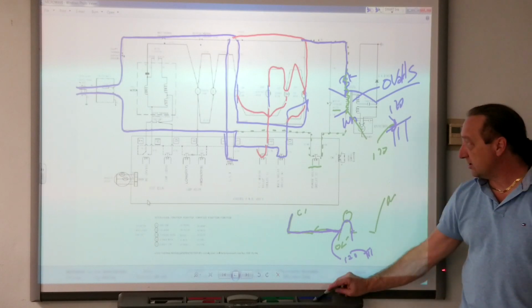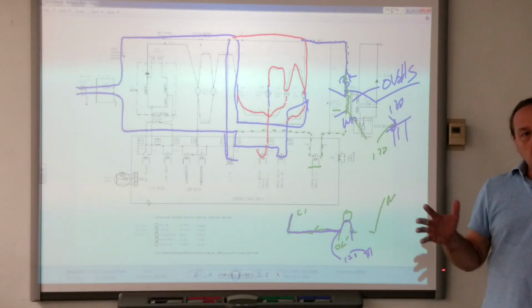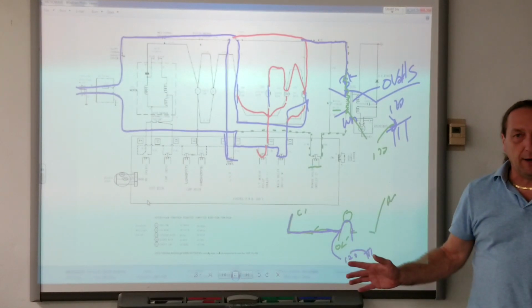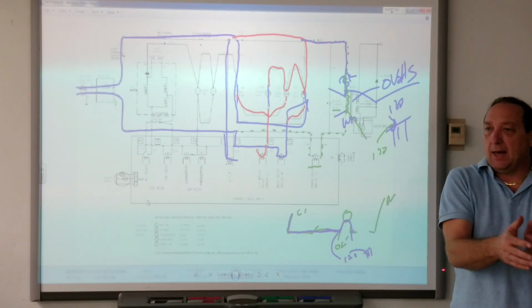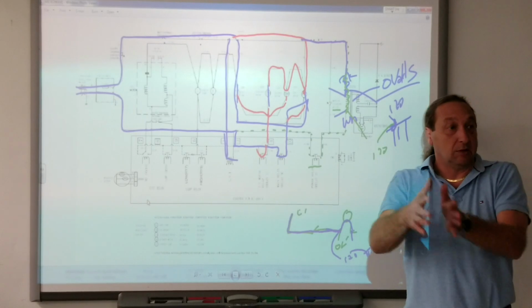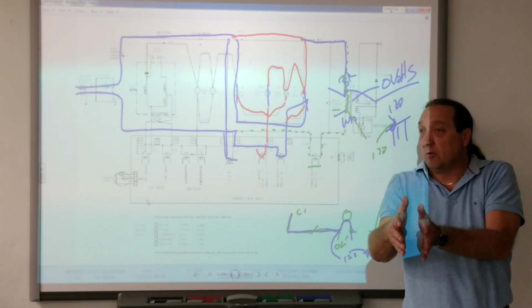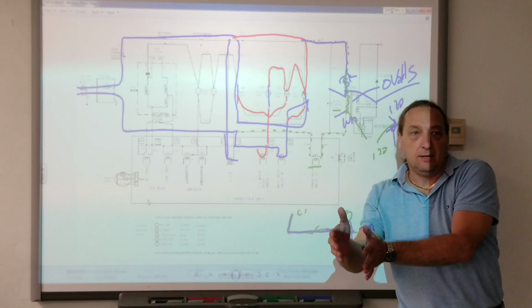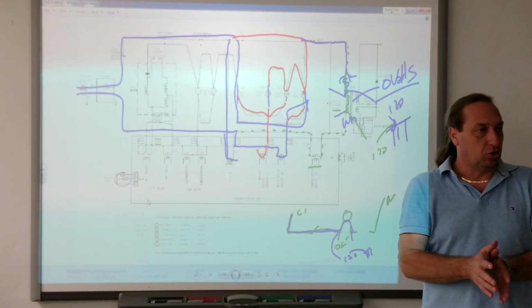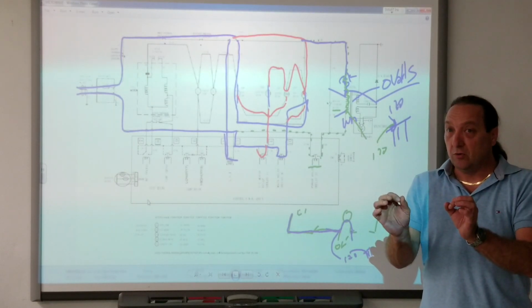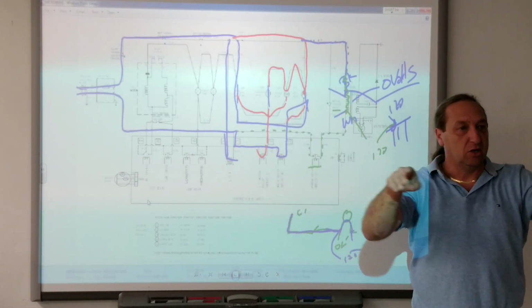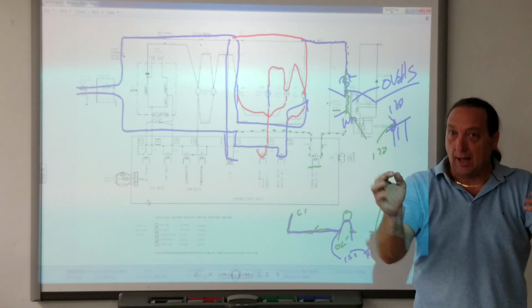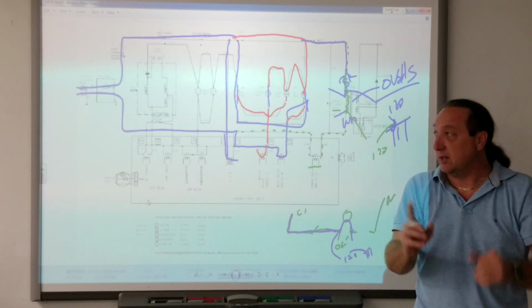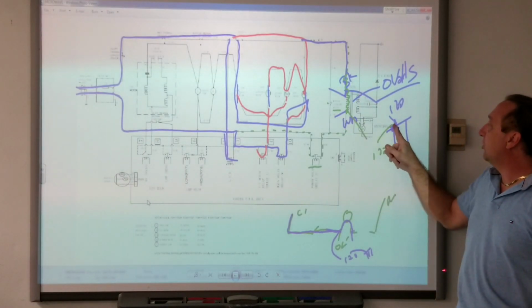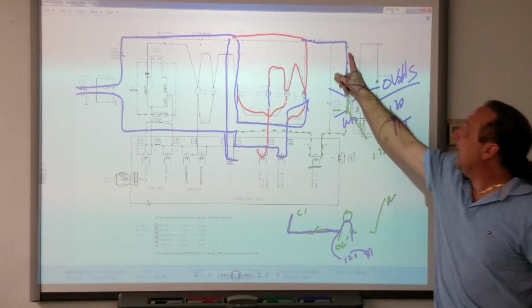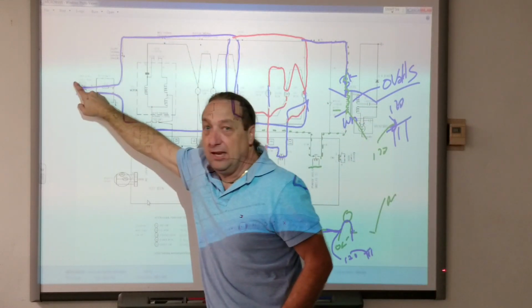Now watch what happens. When we test a circuit with switches and wires, the switch could be bad or the wire could be bad. The load can be bad, which is the light bulb, transformer, whatever, or the wire can be bad. When we make a test with voltage, different from ohms, we're testing an entire circuit. We're testing the wires, the switches, and everything. When I checked from here to ground and had voltage, that meant everything in this circuit up to here is good.